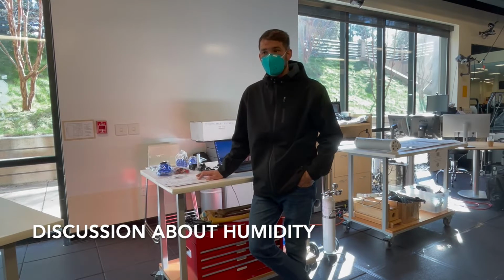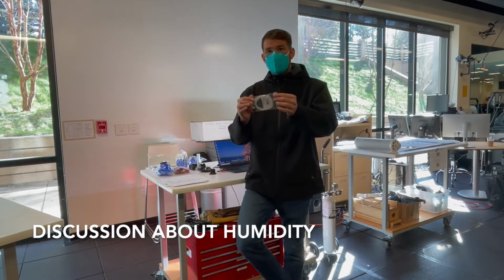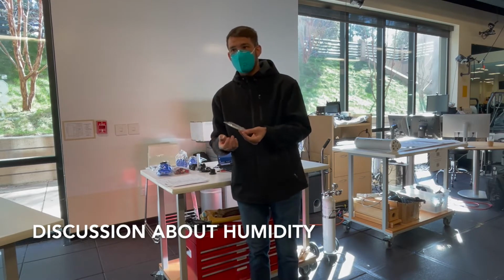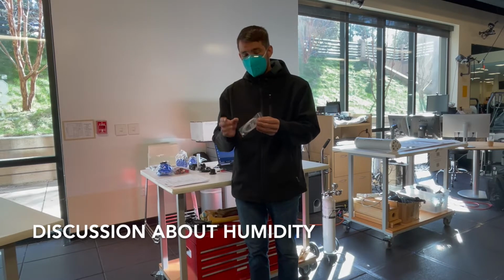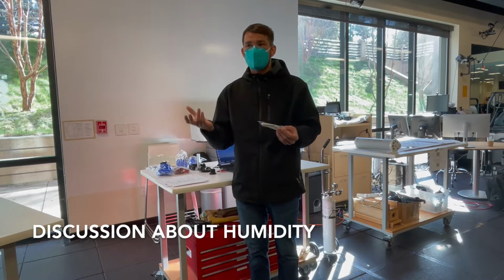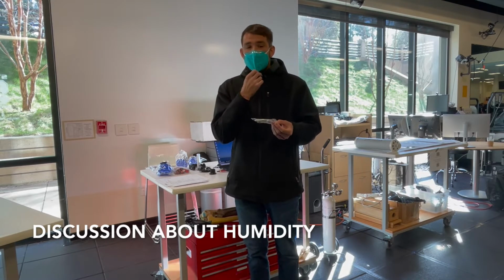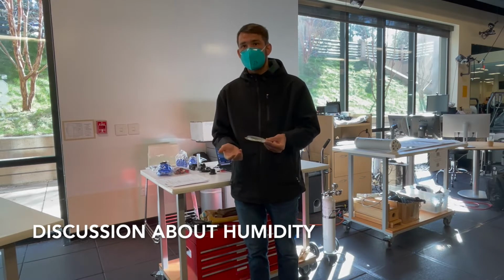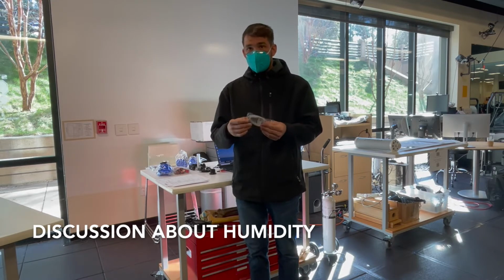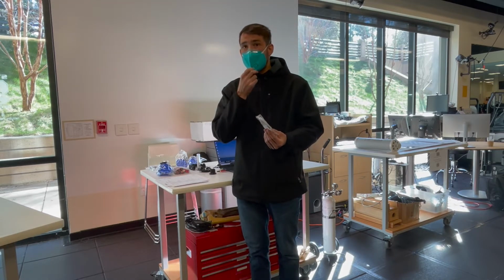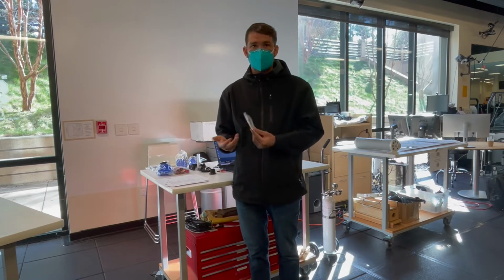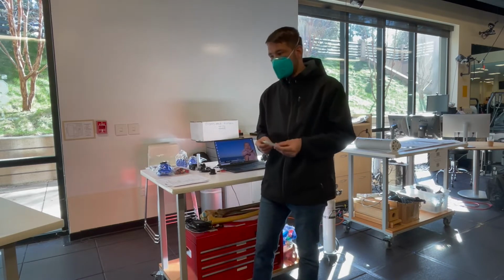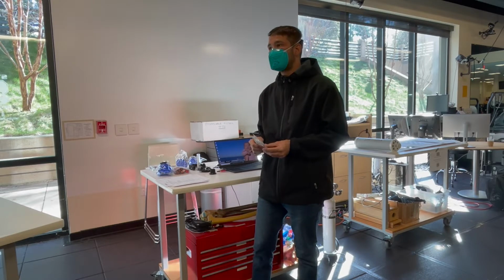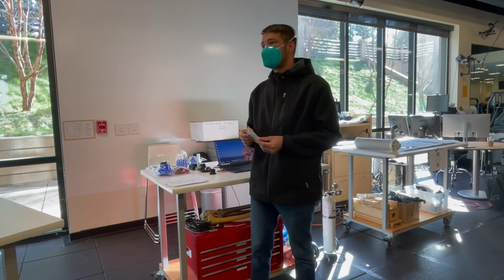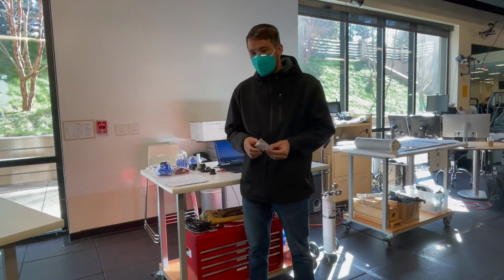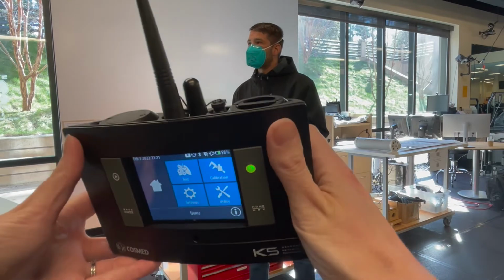And if you get over 90%, what these lines do is, not only are they drawing a vacuum into the analyzer to measure the CO2 and the O2, but they allow humidity to move out of the line. When we expire air, it's always 100% humidified. The analyzers don't want the humidity to be over 50%, and they want it to be stable. So if there's no pathway for water to move out of the line, it's just going to saturate the line and saturate the system, and your data is going to start looking really bad. If it's drizzling out, you would just want to be mindful of what the humidity is, because it can be raining and not really be at 90%. But yeah, you just want to be careful with that.